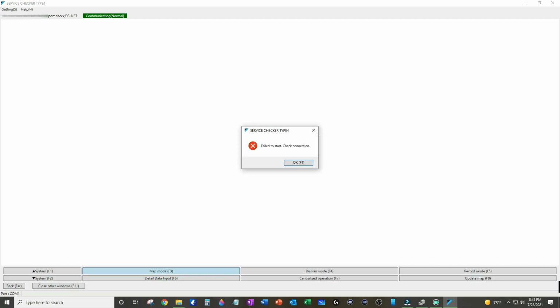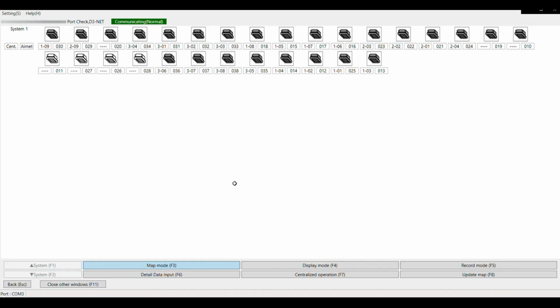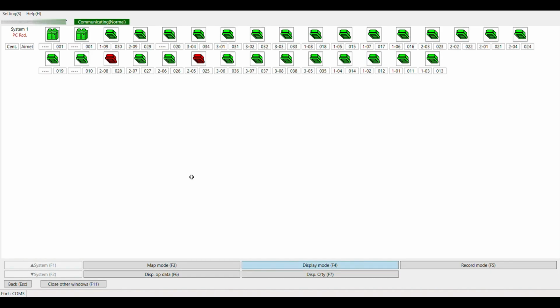Once you've established a proper connection, you will see all the outdoor and indoor icons populate on the network map screen. It's really important at this point to be patient while the equipment populates because it can take a couple of minutes. If you see white icons, this typically means there is a COM issue and the unit cannot pull in for some reason. If you see purple, there is a communication error that's active and needs to be addressed. We didn't have any of the purple icons today, so I don't have those to show you, sorry.